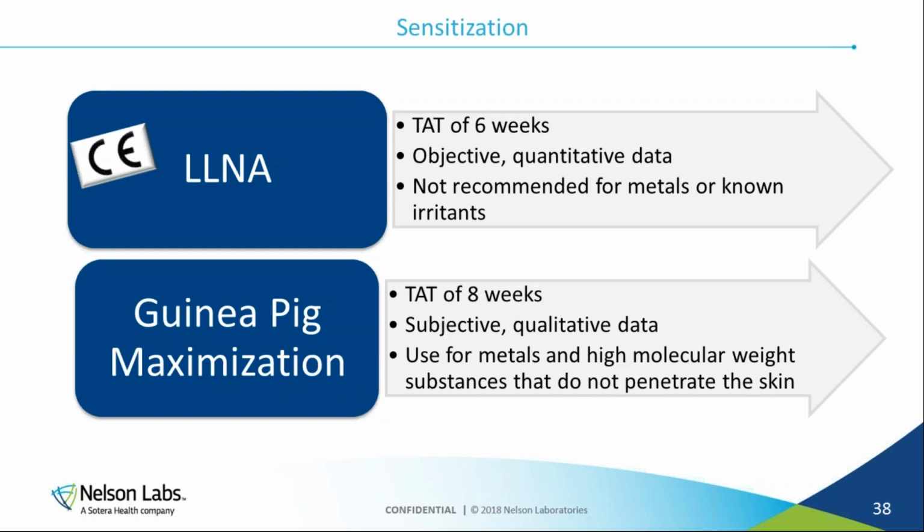So if you're doing a submission for a CE mark, LLNA is accepted, but if you're submitting to the FDA, they would expect to see a guinea pig maximization. So if you are submitting to both markets, we recommend doing the guinea pig maximization test because it is accepted as well for CE mark.